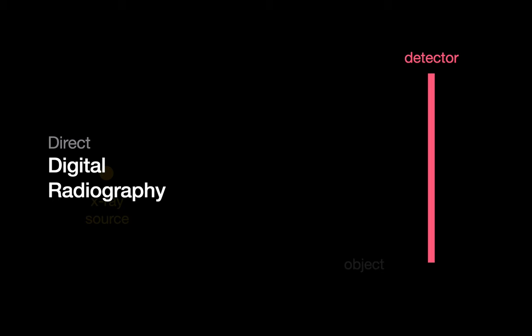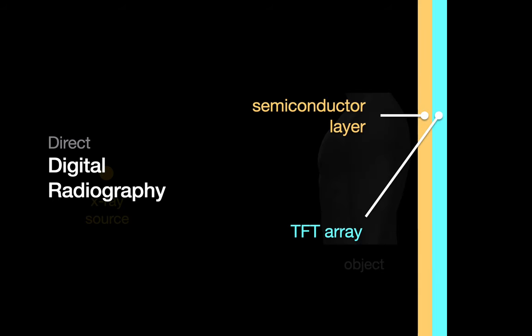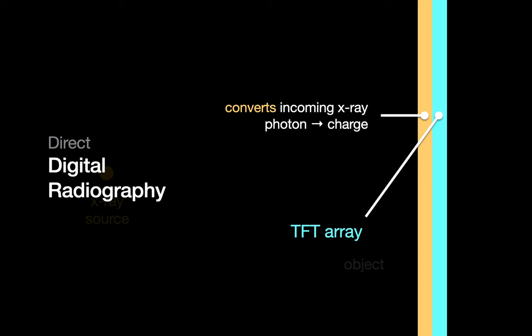With direct DR, a single semiconductor layer replaces the phosphorescent crystal and photodiode layers. Whenever an incoming x-ray photon hits a spot on the semiconductor layer, that event is immediately converted to an electric charge that the TFT panel registers as a black pixel at the corresponding spot. One of the benefits of DR portable chest radiography over CR is that the image is directly created within the detector panel and there's no need for an intervening laser scanning step.